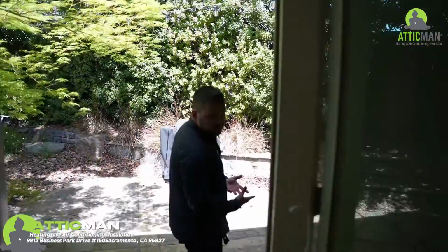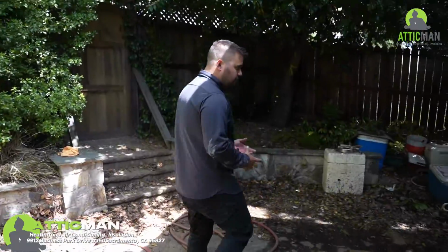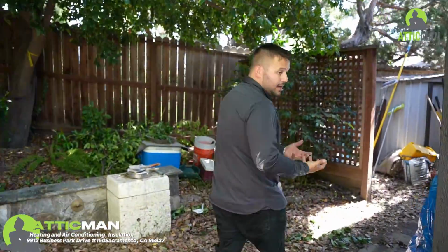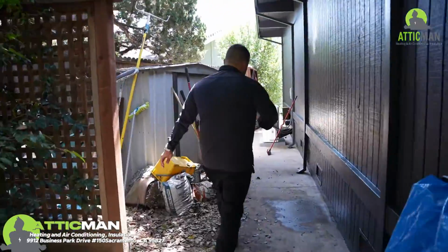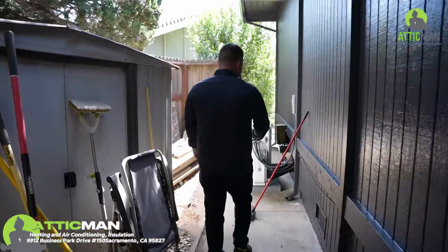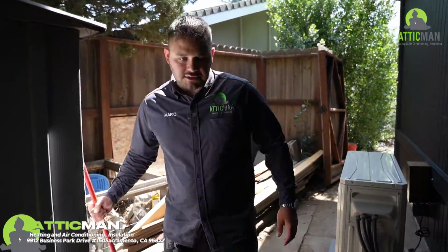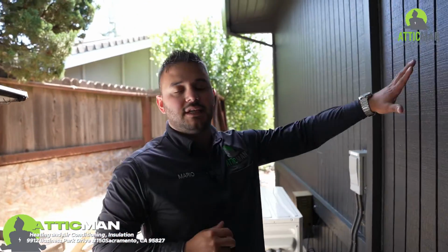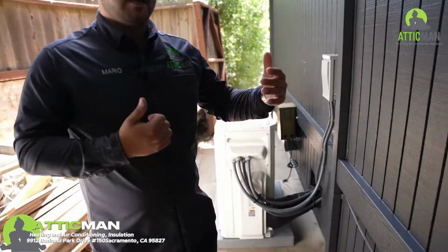Okay, let's go look at the outdoor unit now. So all of these heads connect to an outdoor unit. Sometimes it's one outdoor unit, depending on how many heads you have, 2 outdoor units. This particular project, we decided to go with 2 outdoor units, and that's for a reason. One, the house is fairly large, so the first unit we looked at is completely on the other side of the house. So to get refrigerant lines and electrical lines from there all the way to here is a very, very long run. The longer the refrigerant lines, the less efficient the systems behave and operate. So we wanted to put 2 systems, one on one side, one on the other, so we could make sure that we get maximum capacity.